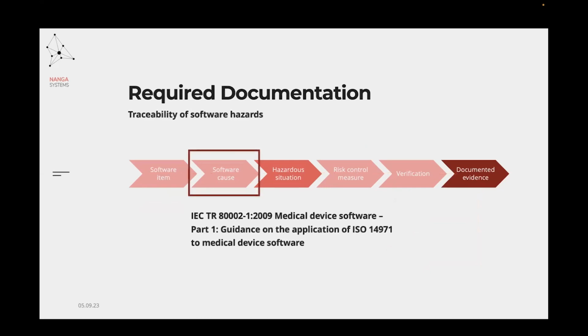In case of the traceability of software hazards, we are focusing on software causes. To start, listing out potential software causes related to a software item might not be the easiest task in the beginning, but a great inspiration can be the document that you can see on the screen, on the slide. Here we have some potential software causes that might be applicable for your medical device software.